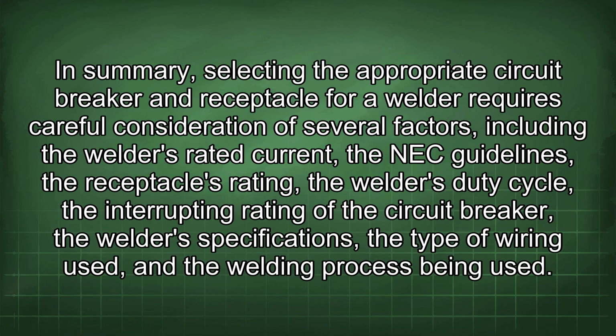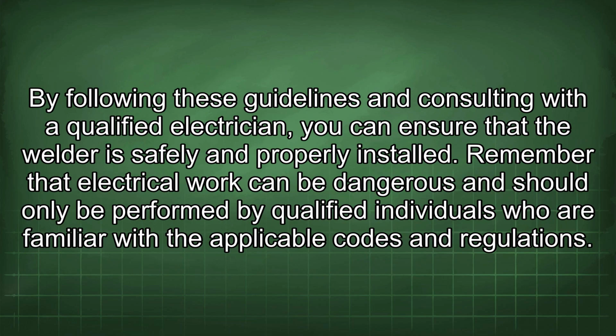installation. In summary, selecting the appropriate circuit breaker and receptacle for a welder requires careful consideration of several factors, including the welder's rated current, the NEC guidelines, the receptacle's rating, the welder's duty cycle, the interrupting rating of the circuit breaker, the welder's specifications, the type of wiring used, and the welding process being used. By following these guidelines and consulting with a qualified electrician, you can ensure that the welder is safely and properly installed. Remember that electrical work can be dangerous and should only be performed by qualified individuals who are familiar with the applicable codes and regulations.